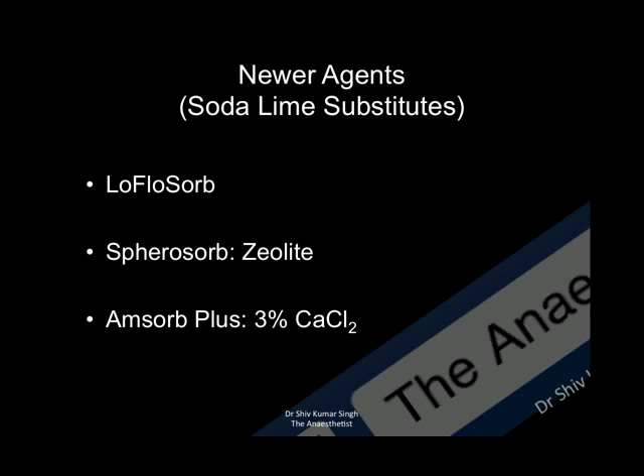There are newer soda lime substitutes: LoFloSorb and Spherosorb, which contain zeolite, and Amsorb Plus, which does not have any hydroxides — it only has three percent calcium chloride.